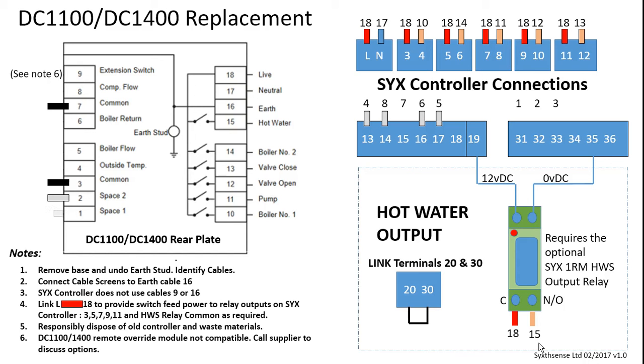Space sensors, if they're available, terminal 1 will be moved onto terminal 31 of the SYX controller, and terminal 2 will move onto terminal 32 of the SYX controller. So the SYX controller will use the average of the two. You should then be left with the sensor commons, and these can be split as required between sensor terminal connection 15 and the ground common connection 33. 15 and 33 are common to each other, and you can mix and match the commons of all the sensors across those two terminals as you see required, or as your cable lengths permit.